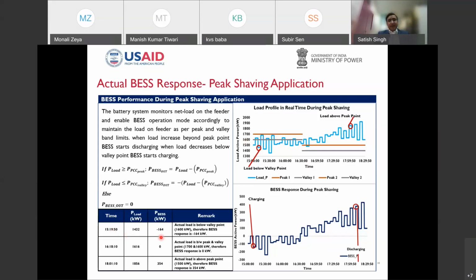My intent is to keep the import from the grid between these two ranges. Accordingly, if the actual load observed at that time was 1432, which is less than 1600, the battery is charging so as to maintain the total import from the grid at the 1600 level. These are the actual BESS responses.